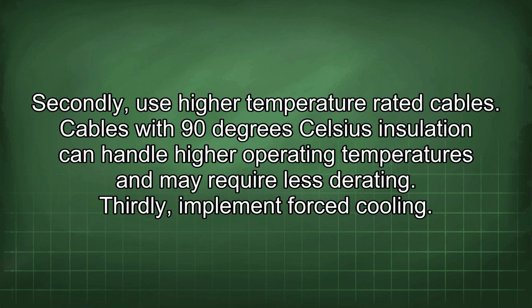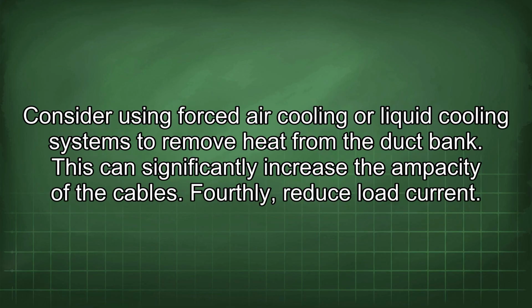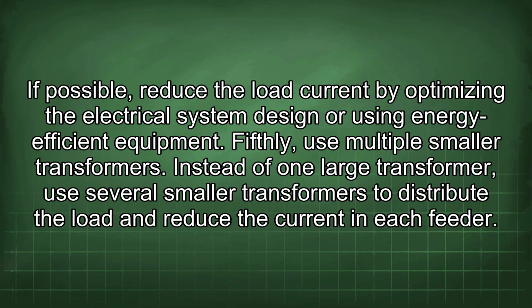Secondly, use higher temperature rated cables. Cables with 90 degrees Celsius insulation can handle higher operating temperatures and may require less derating. Thirdly, implement forced cooling. Consider using forced air cooling or liquid cooling systems to remove heat from the duct bank. This can significantly increase the ampacity of the cables. Fourthly, reduce load current. If possible, reduce the load current by optimizing the electrical system design or using energy-efficient equipment.